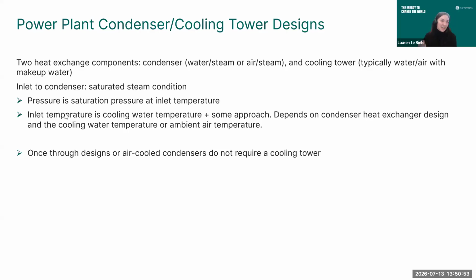This slide lays out that you either work only with water to air directly, in which case you don't need a cooling tower at all, or you do water to water and then a secondary heat exchanger which is water to air. Your final temperature depends on the approach temperature you can achieve with the heat exchanger you select. For an air-cooled condenser, it's just the approach temperature you can achieve with the condenser. For a water-cooled condenser, you have to consider both the possible approach temperature of the condenser design as well as the cooling tower.